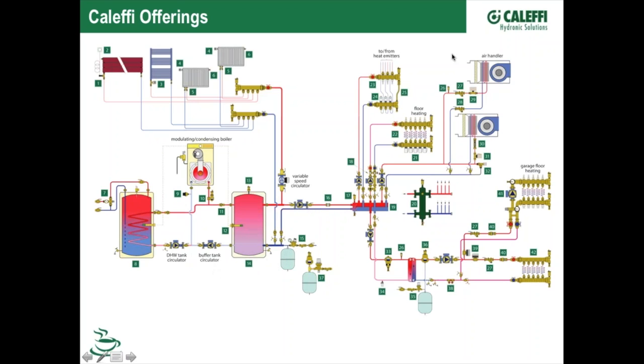So, as you add more and more pumps here and you get further out in the system, you're getting further away from this point of no pressure change. We can't have that exactly right at the suction side of every pump in the system as we start going out to remote manifolds that have pumps out here, or we've got a HydroLink a distance apart. But that's the key, is we want to pump away from that point of no pressure change, the expansion tank connection, as close as possible to that. And that's what we're showing here.